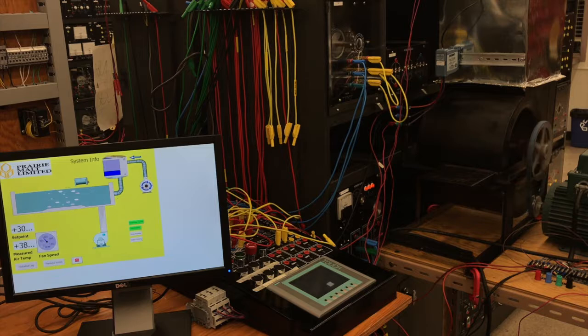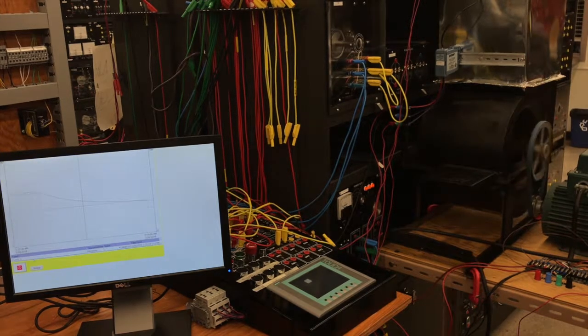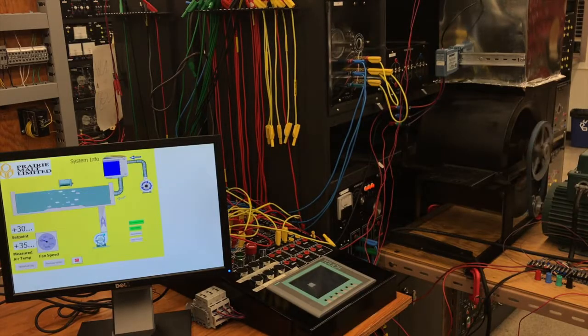Now we're going to change the preset again to another temperature. And you can see the target preset line has gone down, and now the system is trying to bring the temperature down to meet that. So it's added some more fan speed, and you can see the trend line dropping. And just like the other changes in temperature, as the trend line gets closer, it slows the motor down.